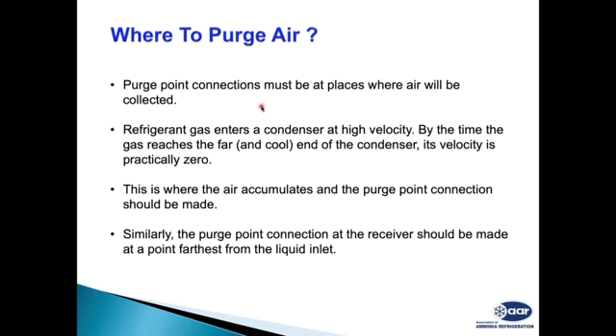Now this air, at the entry point of the condenser, will be at the same velocity as the ammonia. So if we try to take a purge point from the inlet of the condenser, then our ammonia will come out. Let's say we have 5% air in the plant. When we open the inlet purge valve at the inlet of the condenser, 5% is air and 95% is ammonia, so 95% ammonia gas will go to the purger. So it will not work. We have to choose purge points where there is minimum presence of ammonia gas, and we are able to separate the ammonia from the non-condensable gases or air.